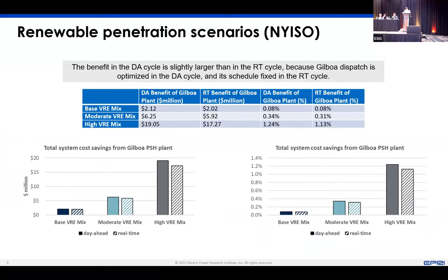But here, total system cost savings for the Gilboa pump storage plant. The way we evaluated that is running one case with and one without the pump storage and looking at the delta in terms of system costs or production costs between the two. And you'll notice the base, moderate, and high renewable mixes. One figure here, the first one, is in millions of dollars, and then the second one is in percentage of cost savings, and that'll show up a few times in my presentation. But what we notice right off the bat is a fairly modest system cost savings in the base case, but then those increase fairly significantly in the moderate, and then especially in the high VRE mix case.